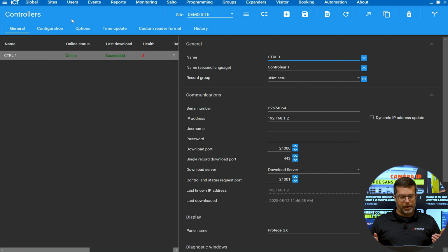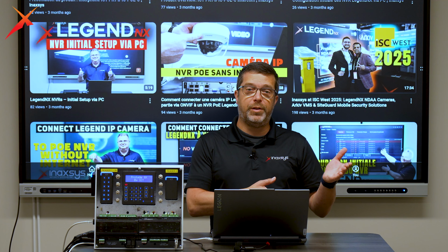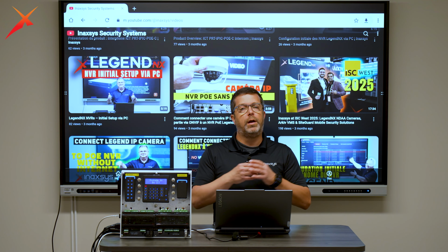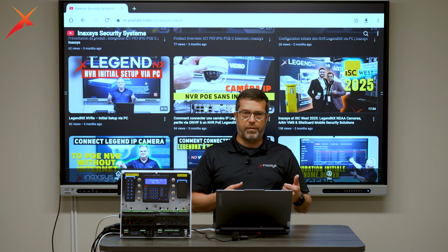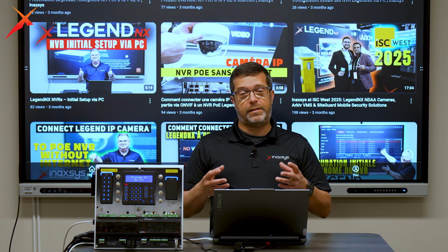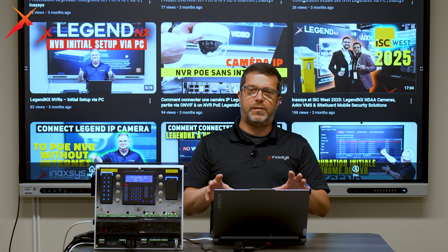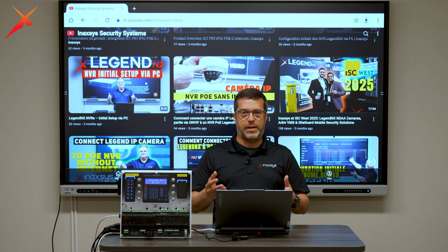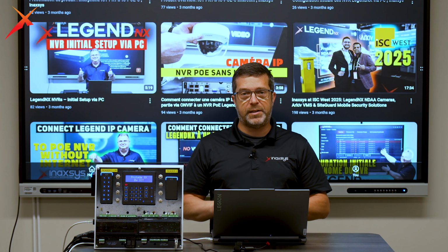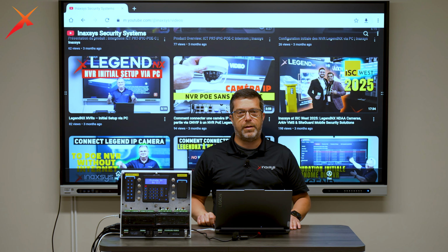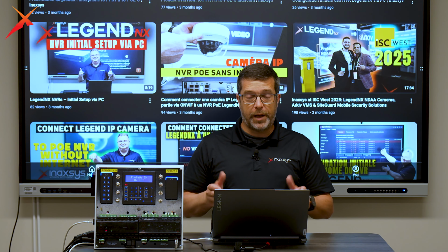So now we have the controller online, the controller updates the time automatically, we have events coming in, we have a backup done every night, at least of the main database, and in theory the database will never be full because it's going to truncate older events on a daily basis at midnight. I hope the tutorial helped you. It's a way to have the basic settings that are important done in your GX system. Now you can start adding more modules, users, and access levels, but at least you have a system that will maintain itself in terms of daylight saving time change, and also the database that will be saved on a daily basis.